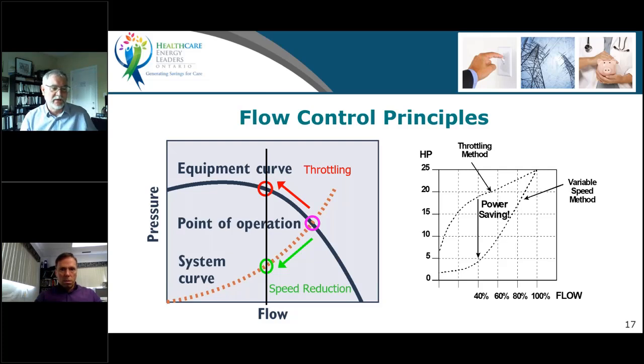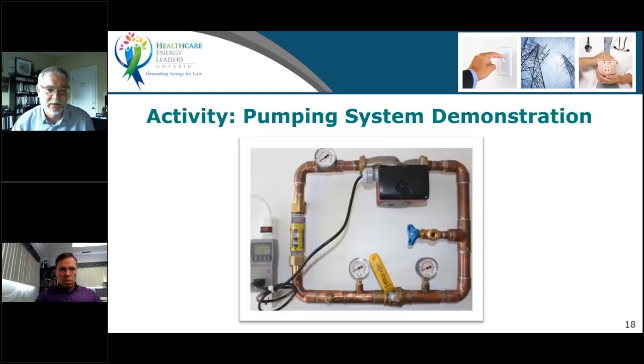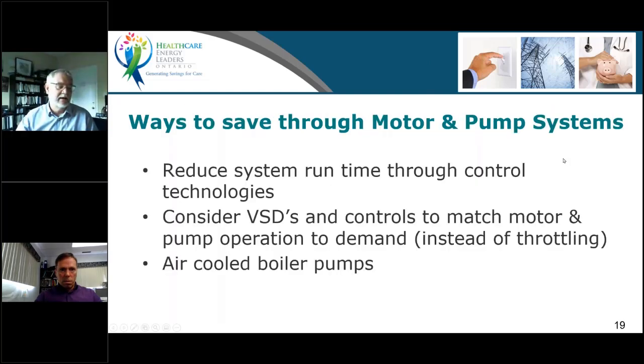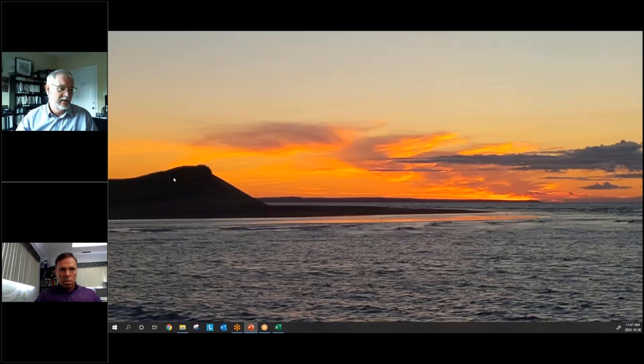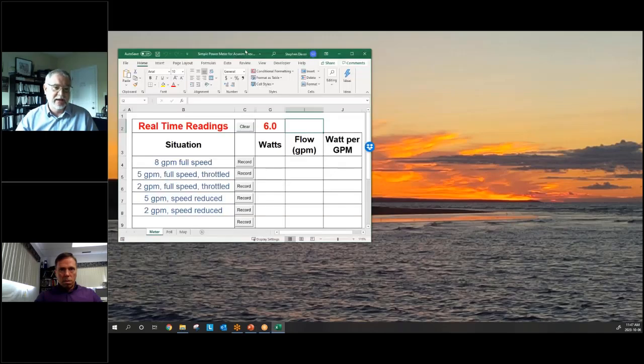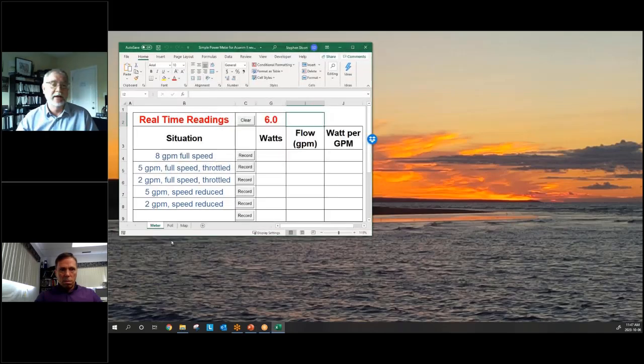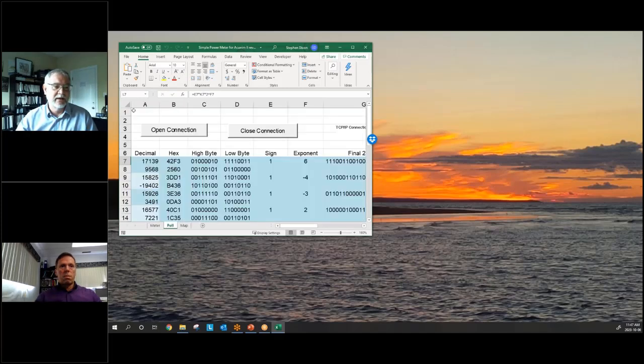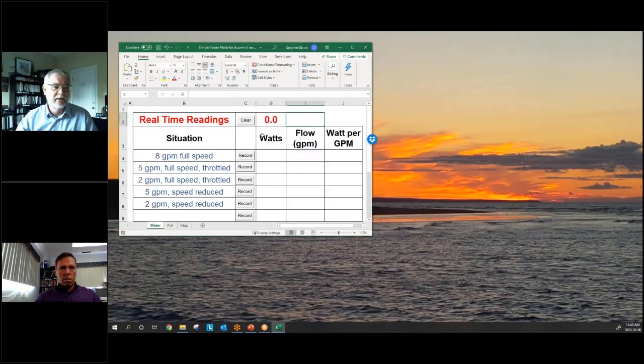So what I want to do, just to finish off before lunch, is to actually demonstrate this firsthand. So I'm going to take down my slides here, and you're going to see a great little sunset picture in a second. And I'm going to open up my electronic flip chart. It's actually a spreadsheet connected to a flow meter and a power meter that's driving a little pumping system I'm going to show you in a second. So I'm just going to start up my connection to this system. Here we go. Right now it's showing 0 watts. I'm just going to test it. I'm going to turn my pump on, and I can actually see the wattage.